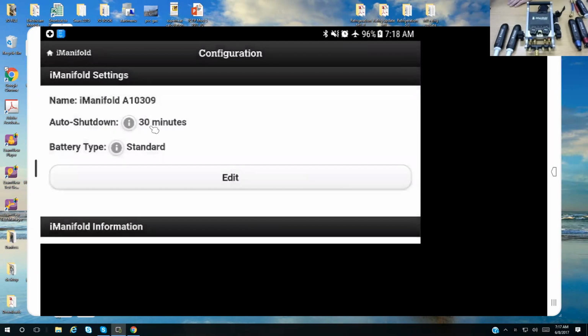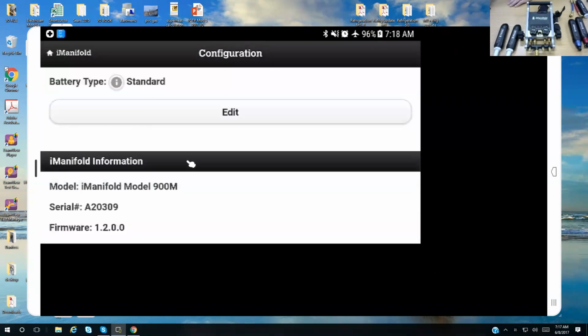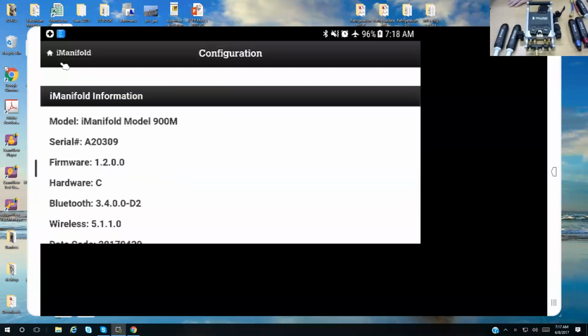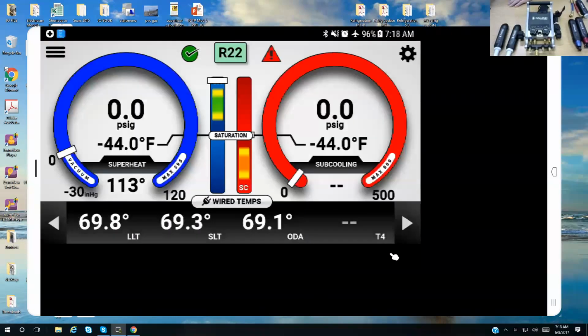All right, so I changed it to 30 minutes. We're using standard battery. This is the configuration menu. All right, we're back here on the home screen. We can see the temperatures being measured. We're paired up to the iManifold and both of our probes. Here's our air side, the return and supply, probe 1 and probe 2.